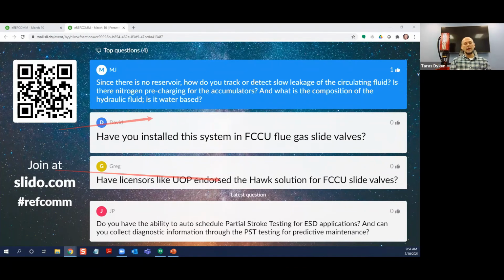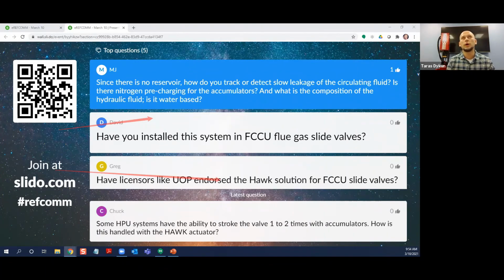And if you wouldn't be able to, you would actually be able to notice it from the diagnostics and stuff. So additionally, these can come with pressure transmitters, which can also monitor the actual pressures inside each side of the cylinder. As you saw in the video, we had the pressure gauges there. We can install the pressure transmitters, and you can monitor the developed thrust and pressure of this unit and track it back to your DCS, or we can alert you if there is something unusual going on, or if we're not able to build up enough pressure to position the actuator. So probably the only thing which can leak by is the piston seals. So hopefully I answered that question.